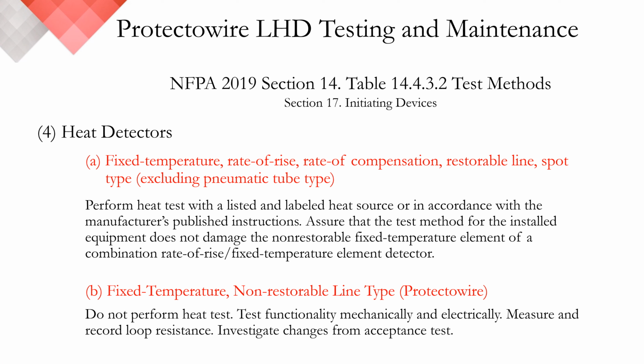Protectowire is identified as a non-restorable line type heat detector, and as such, NFPA guidelines do not require a heat test be performed, as it would damage the non-restorable device and require immediate service. Rather, it requires a functionality test be performed. Electrically, all that's required is the detector is shorted at the end of line zone box. The ability to induce an alarm or a fault condition from this point verifies the integrity of the detector.